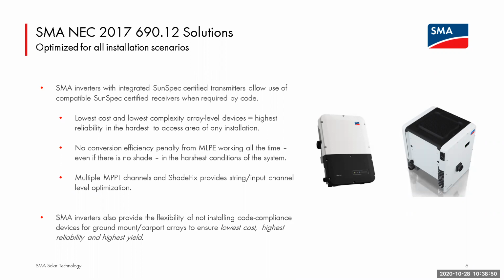Those devices are in the environment and the locations that your crews really don't want to get into. So they're never on the corner of the array. They're typically in the middle of the array, tough to locate, tough to replace. So again, by choosing SMA, you're keeping the heavy lifting, if you will, down at the inverter level. In exchange, that leads to fewer truck rolls, higher reliability systems for you and your customers.